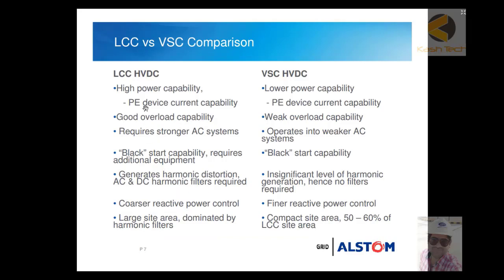Further comparison: LCC has high power capability based on PE device current capability, whereas VSC HVDC has lower power capability. LCCs have good overload capacity while VSCs have weak overload capacity. LCC requires a stronger AC system whereas VSC can operate into a weaker AC system. For black start capability, LCC HVDC requires additional equipment, whereas VSC HVDC does not require additional equipment. LCCs generate significant AC and DC harmonics requiring harmonic filters, whereas VSCs generate an insignificant level of harmonics and hence no filter is required — this is a key advantage of VSC.